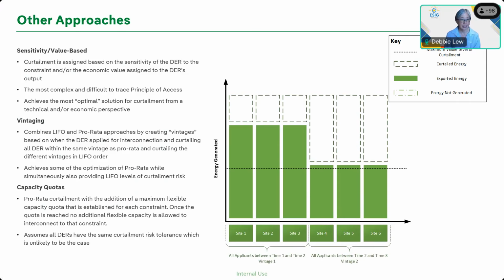Nice. Thank you. Someone asks, is the hosting capacity defined per node? So technically, dynamic hosting capacity could be defined per node. As mentioned previously, we're only focusing on substation and feeder level, feeder exit conductor level constraints. So it wouldn't make sense to define dynamic host capacity per node, partially because you'd also need to have monitoring or some way of tracking that to be able to define the dynamic capacity at every node. Good point.